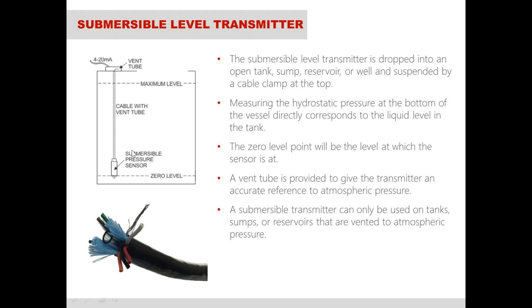You can only measure the level from the zero level where that sensor sits. Anything above that, you can measure the hydrostatic pressure, basically the weight of the liquid on top of the pressure sensor. For instance, if you had 10 feet of water on top of this sensor, you would have 10 feet of water column of pressure on the sensor.